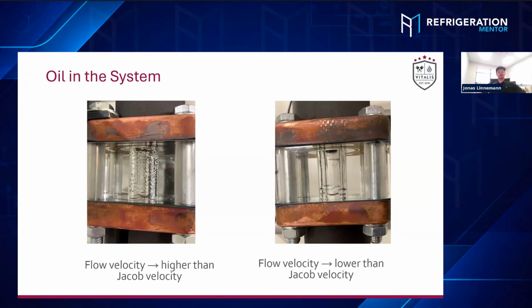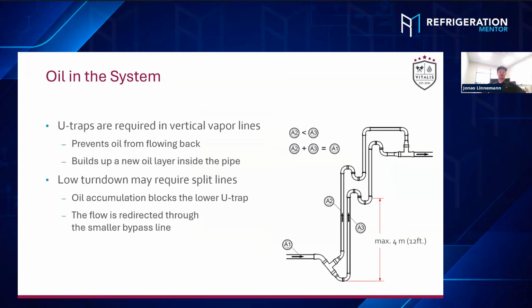And if you run into very low part load conditions, that's when you're coming to these double risers, right? So the general idea of these U-traps, even with just a single riser, is that every few meters, like every 4 meters of height, you would have this U-trap. And as I mentioned before, the oil is traveling in a thin layer up the vertical pipe, and it's getting thinner and thinner the higher it climbs. And by these little U-traps in between, you basically just rebuild this oil layer, and then it can start again to travel up. So theoretically, you can go as high as you want as long as you build every 12 feet or 4 meters a U-trap.